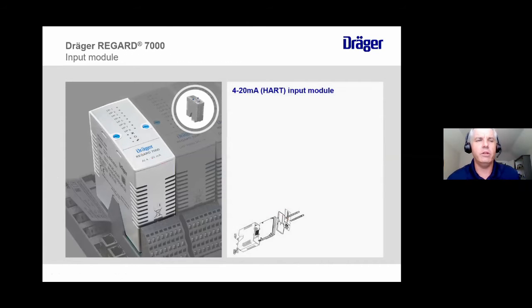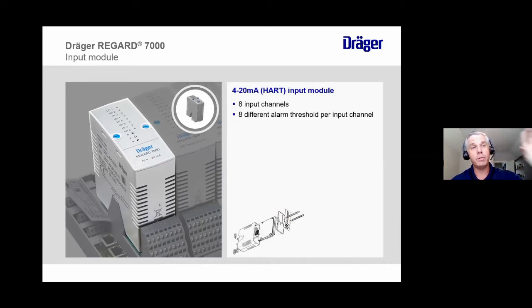So let's talk about the go-to for most of these applications, which is going to be our 4 to 20 HART input module. Like I mentioned, we have a regular 4 to 20 input module, but for the most part, you just want to use the HART one, because a lot of the features go away if you just have a straight 4 to 20 from the transmitter to the controller. Once you have the HART, you get all the diagnostics you can pick up as well. So most times we're going to go with the HART module. Up to 8 input channels you can put on one module, and you have up to 8 different alarm thresholds per input channel. So potentially on one input module, you can have 64 different alarm set points.